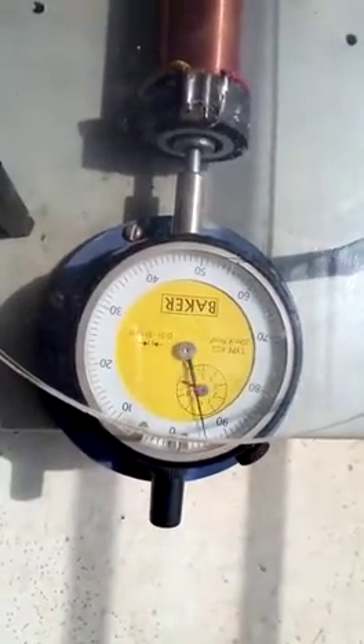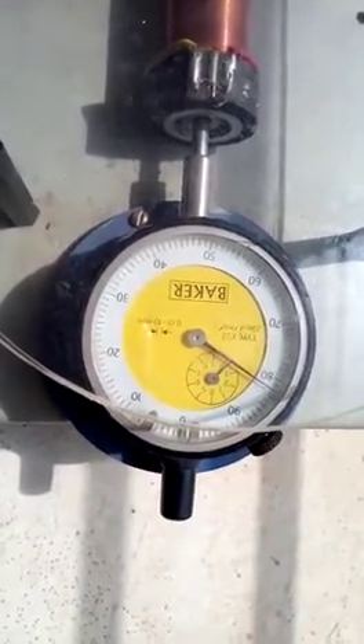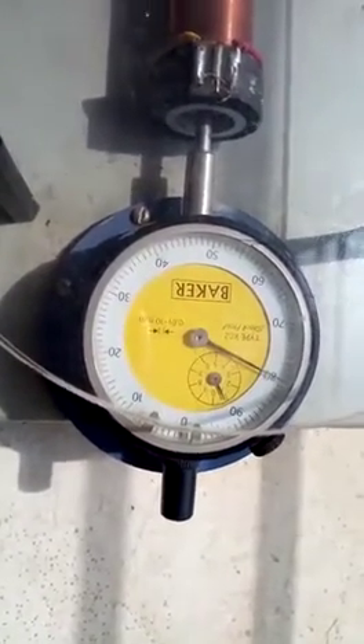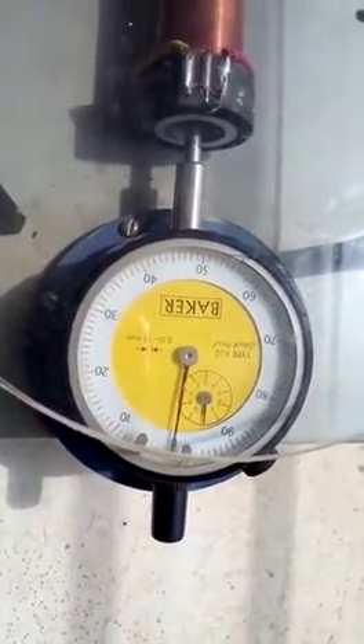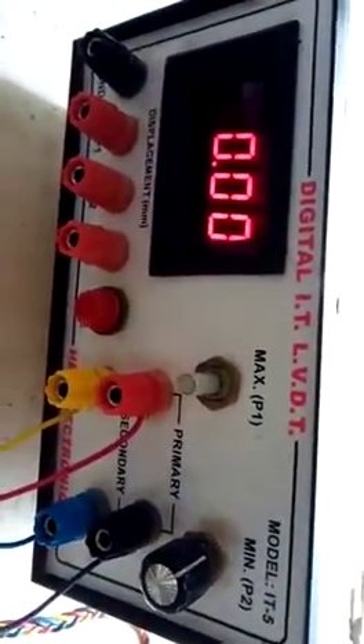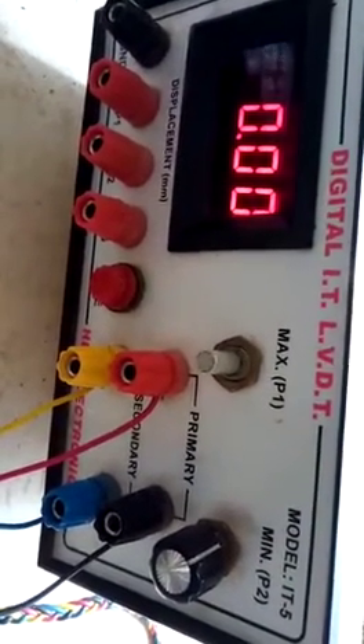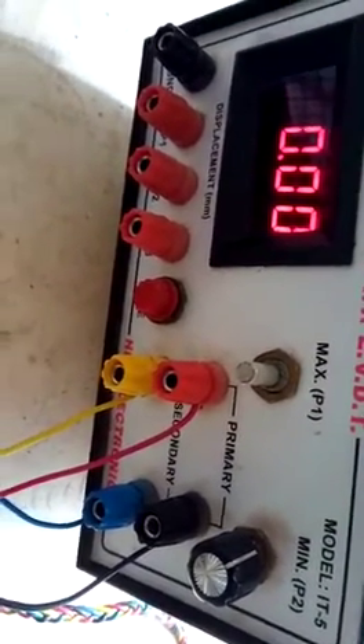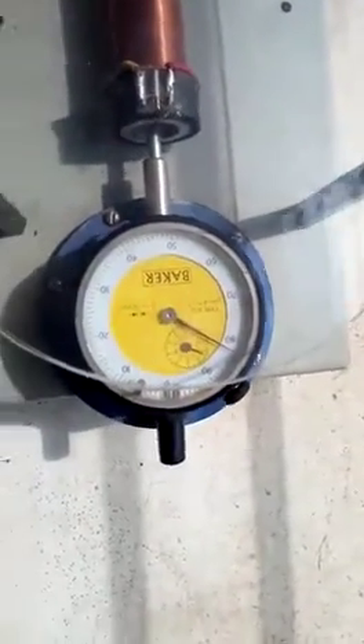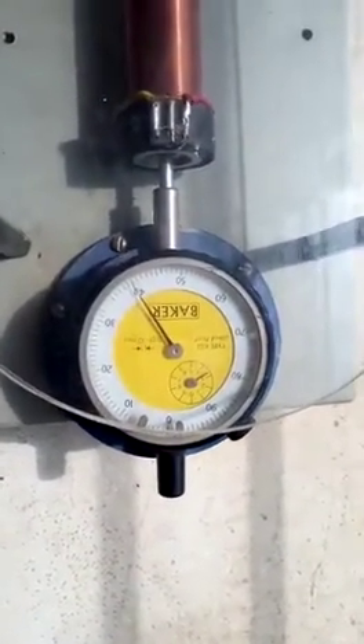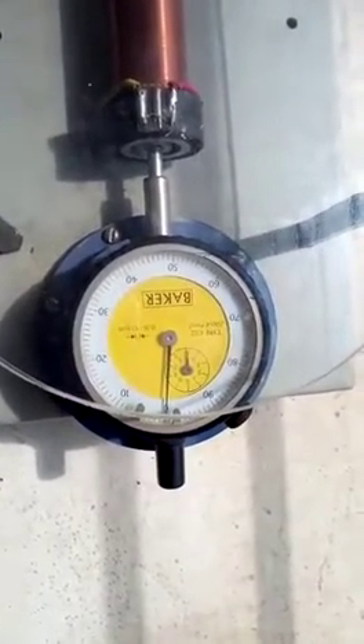Rotate the knob of the LVDT in anti-clockwise direction to displace core in backward direction to minus 10 mm position. Before we rotated in clockwise, it was showing 10 mm. Now we rotated in anti-clockwise. Now it is showing 0 reading. Now we should repeat the same for 6 to 7 readings, and now the given LVDT is calibrated.